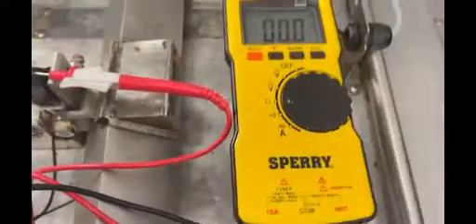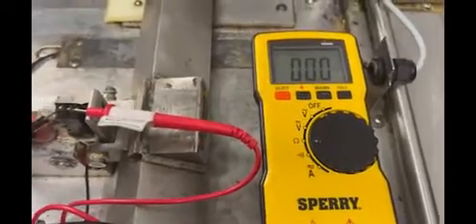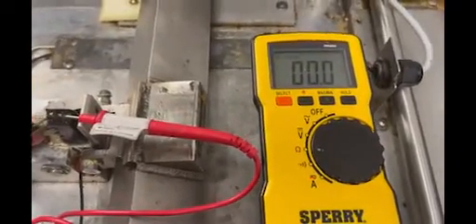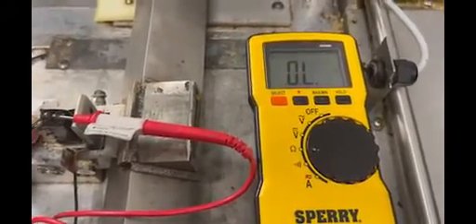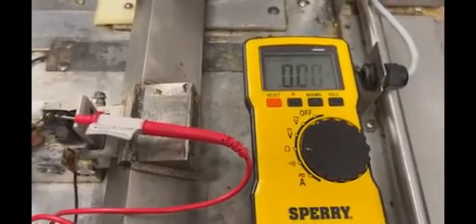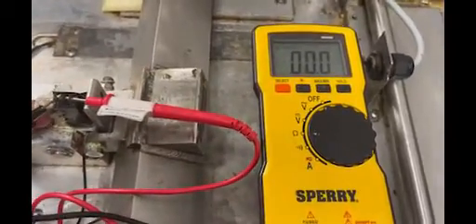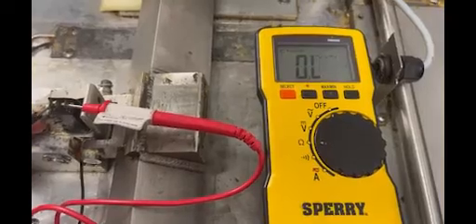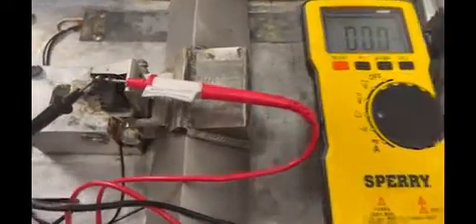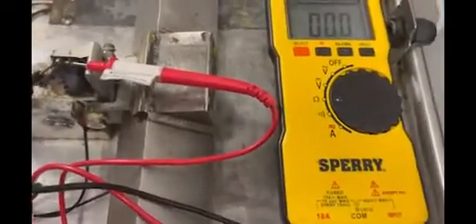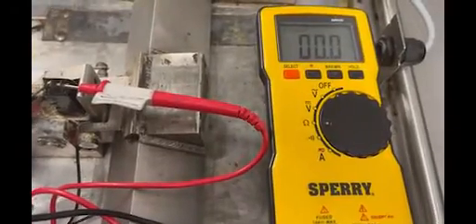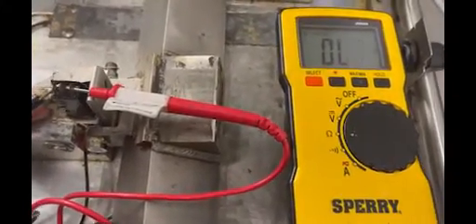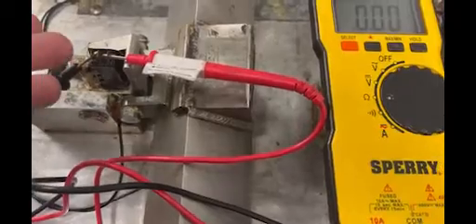You can also test this component with a voltmeter. I've put my leads on the two outer terminals and I'm showing continuity, but as soon as I lift up on the spring, it should go to open line, which it did. So it has continuity, and when it goes under pressure, it's an open line. That's one way to test that. If it was staying open the whole time, or if it wasn't opening at all when I lifted the pin, I would know there are issues with the switch.